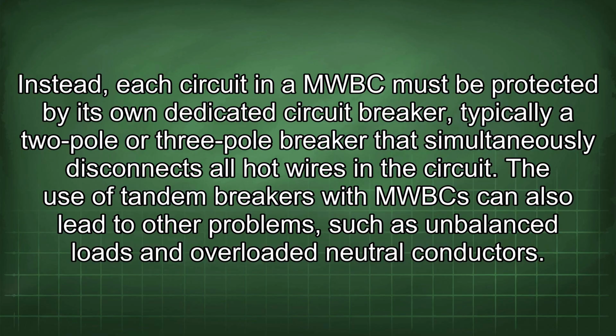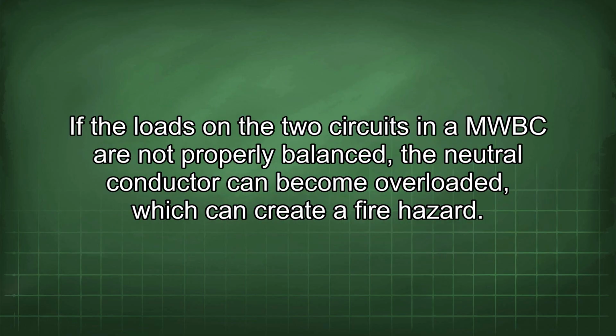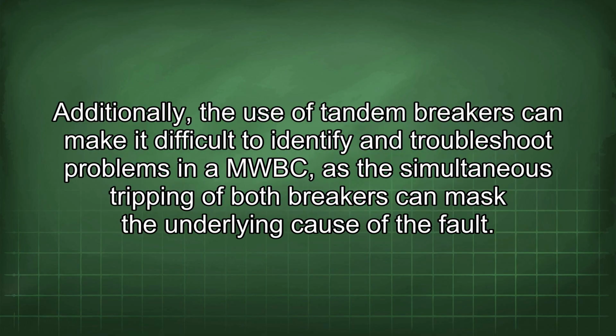The use of tandem breakers with MWBCs can also lead to other problems such as unbalanced loads and overloaded neutral conductors. If the loads on the 2 circuits in the MWBC are not properly balanced, the neutral conductor can become overloaded, which can create a fire hazard. Additionally, the use of tandem breakers can make it difficult to identify and troubleshoot problems in an MWBC, as the simultaneous tripping of both breakers can mask the underlying cause of the fault.